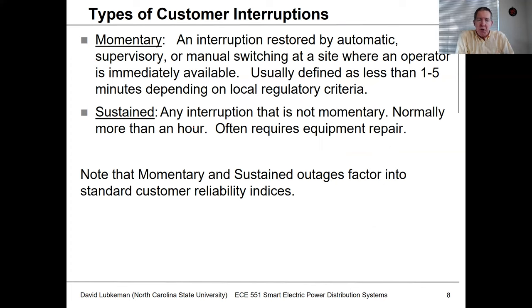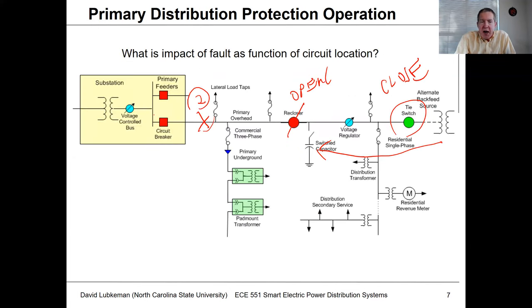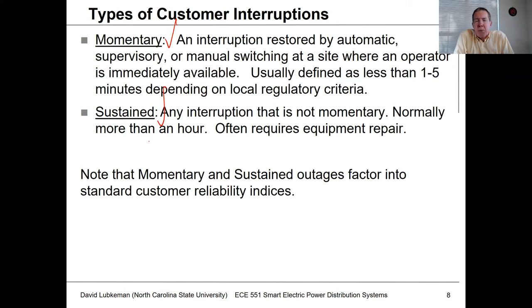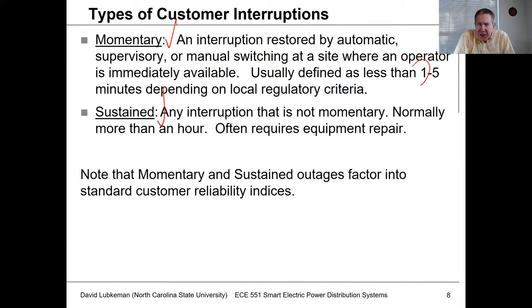We're going to talk about two different types of interruptions — momentary and sustained — although we'll be more interested in calculating the sustained category. If you have a fault that causes a circuit breaker to open, then it recloses back in and the fault's been cleared, that's a momentary event where people see a blink. Events less than five minutes — or depending on the regulatory jurisdiction, maybe one minute — typically don't count against us from a reliability reporting standpoint.